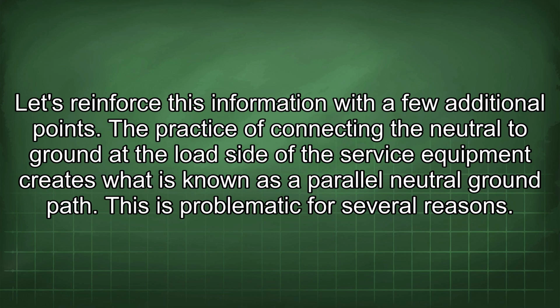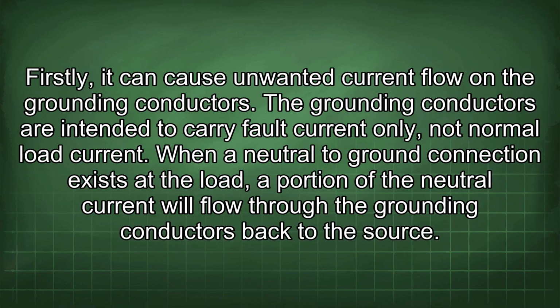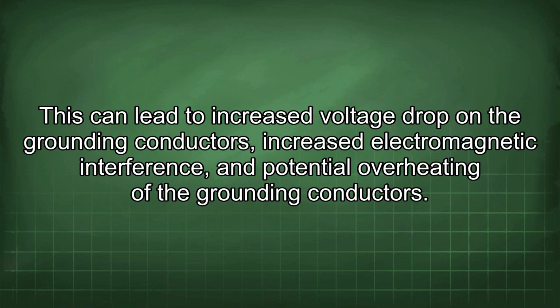The practice of connecting the neutral to ground at the load side of the service equipment creates what is known as a parallel neutral ground path. This is problematic for several reasons. Firstly, it can cause unwanted current flow on the grounding conductors. The grounding conductors are intended to carry fault current only, not normal load current. When a neutral to ground connection exists at the load, a portion of the neutral current will flow through the grounding conductors back to the source. This can lead to increased voltage drop on the grounding conductors, increased electromagnetic interference, and potential overheating of the grounding conductors.